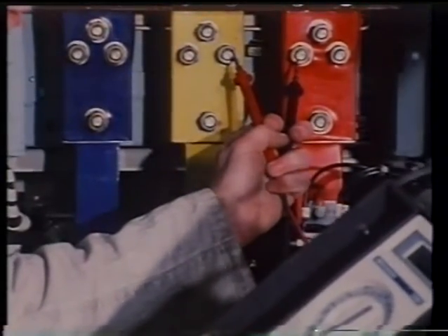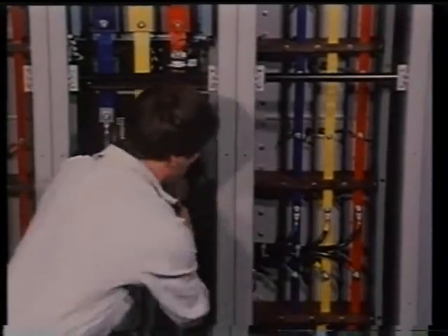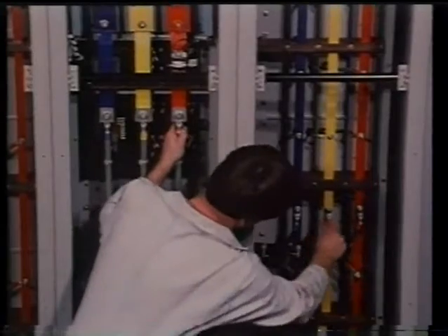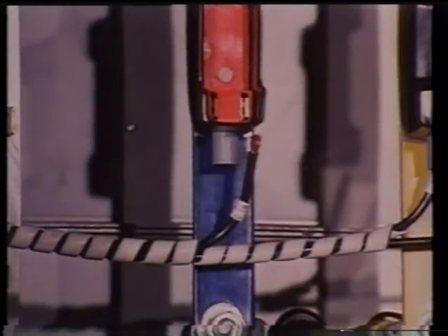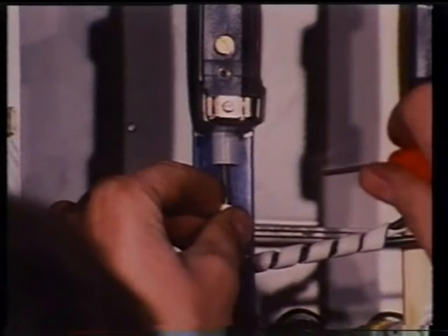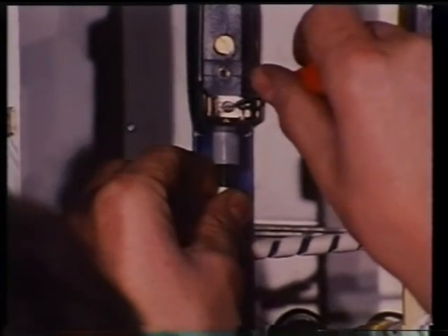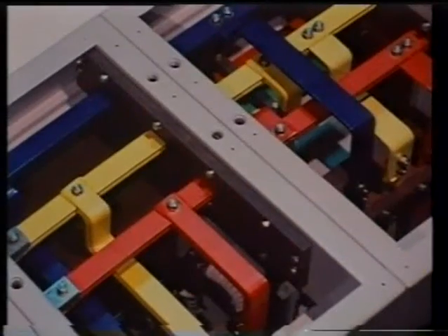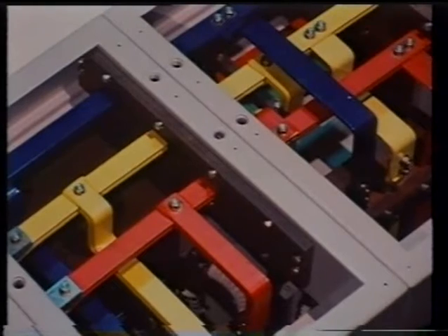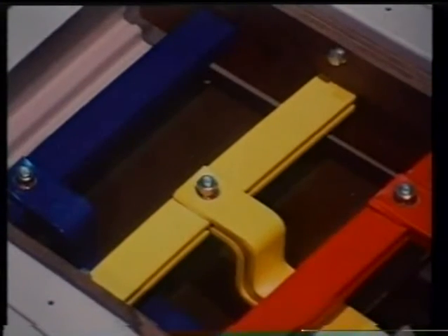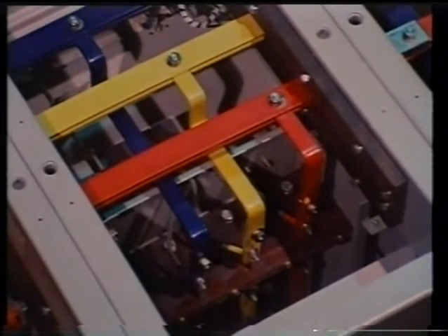Check that the board is dead, then check all internal connections in the main as well as in the emergency switchboard, ensuring that all connections are clean and dry. Any connections which do not prove tight enough must be remade and rechecked. All main busbar and auxiliary connections throughout the boards should be checked for loose joints. Busbar supports should be examined for surface tracking and possible damage to the insulation material.